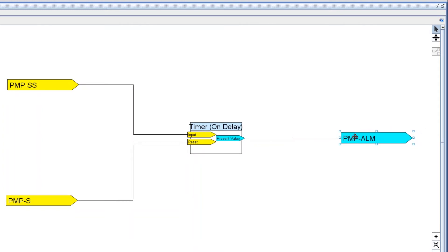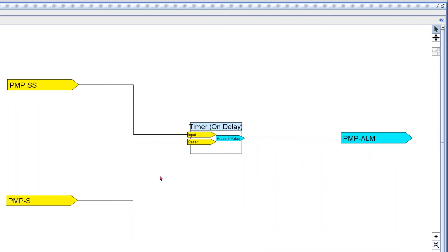This is the very basic setup for this alarm. For this first example, here's how it works: any time we give the pump a start command and we don't get a status within 15 seconds, we get an alarm. Also, if we have a start command and a status but then suddenly lose our status, after 15 seconds we also get the alarm. Now let me show you how this timer works — I'm gonna start a simulation at 1x speed.